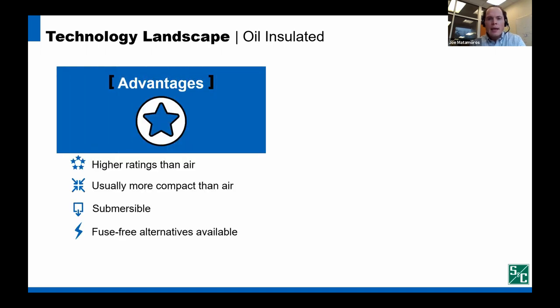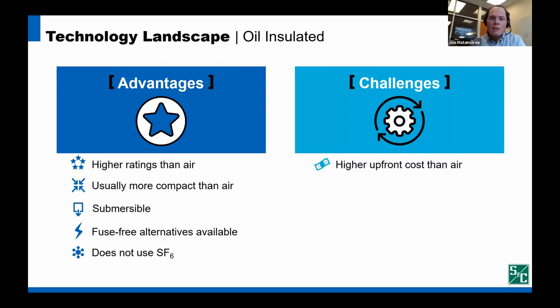Like gas insulated gear, oil insulated gear was developed decades ago. It has several of the same advantages of gas insulated gear. It also has advantages in that it does not use SF6. On the downside, like other submersible gear, it has a higher upfront capital cost than air insulated gear. And then oil insulated gear requires regular maintenance.